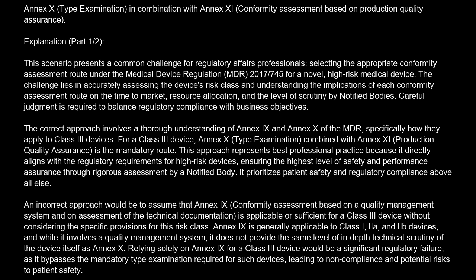For a Class III device, Annex X type examination, combined with Annex XI production quality assurance, is the mandatory route. This approach represents best professional practice because it directly aligns with the regulatory requirements for high-risk devices, ensuring the highest level of safety and performance assurance through rigorous assessment by a notified body. It prioritizes patient safety and regulatory compliance above all else.